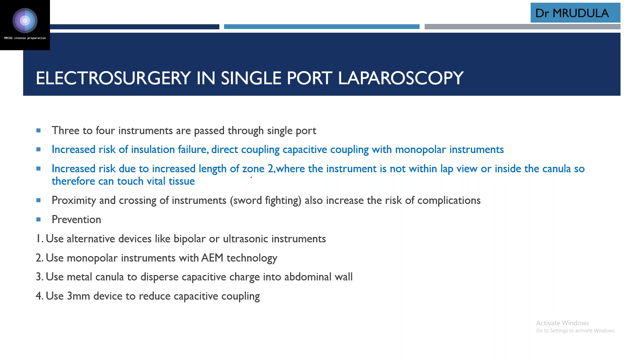Prevention: use alternative devices like bipolar or ultrasonic instruments. Use monopolar instruments with AEM technology. Use metal cannula to disperse capacitive charge into the abdominal wall. Use 3 mm devices to reduce capacitive coupling.